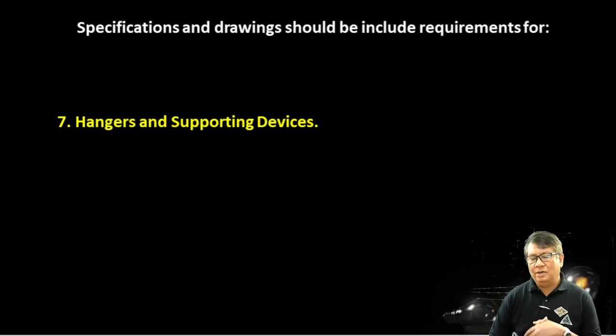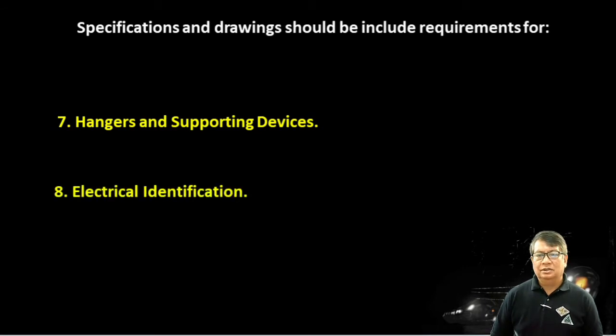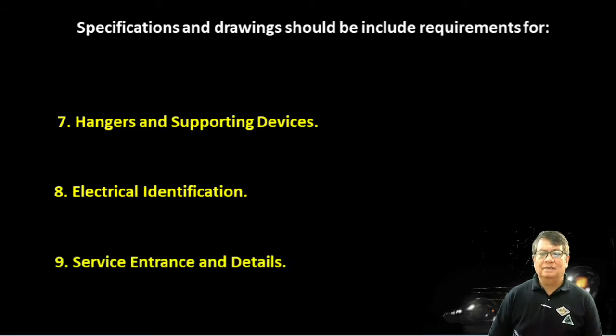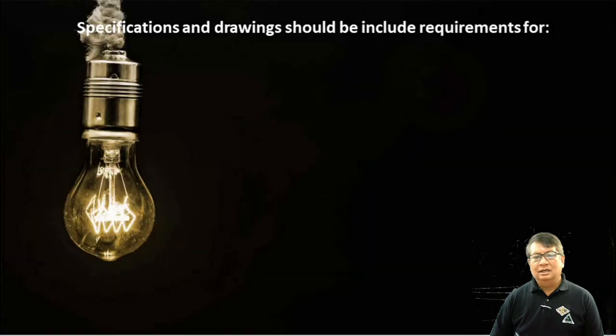Okay, especially if our installation is in the ceiling, we need to have supporting equipment or devices or design. Okay, so hanger, no? So that it is not directly stapled or fixed in the ceiling joist or in the installation, no? So electrical identification. This is necessary so that we will be able to identify which is the hot or the live wire, which is the ground wire, which is the neutral wire, no? So service entrance and details. So the service entrance is the receiving part of the installation from the electrical pole of the distribution utility towards our building. Okay, so service entrance and details is very important.